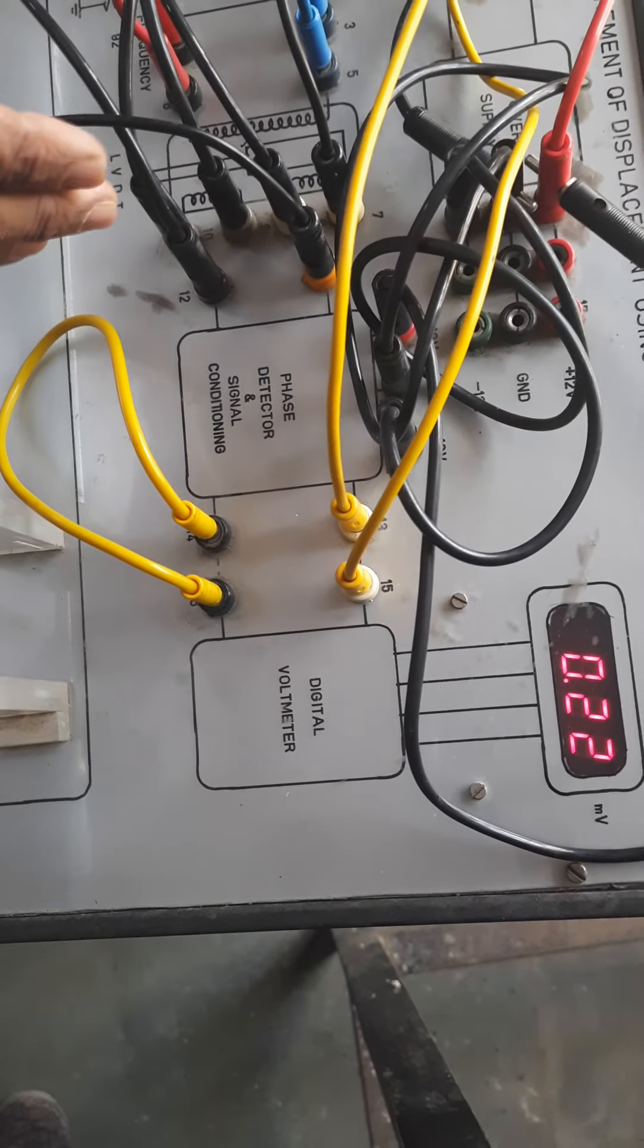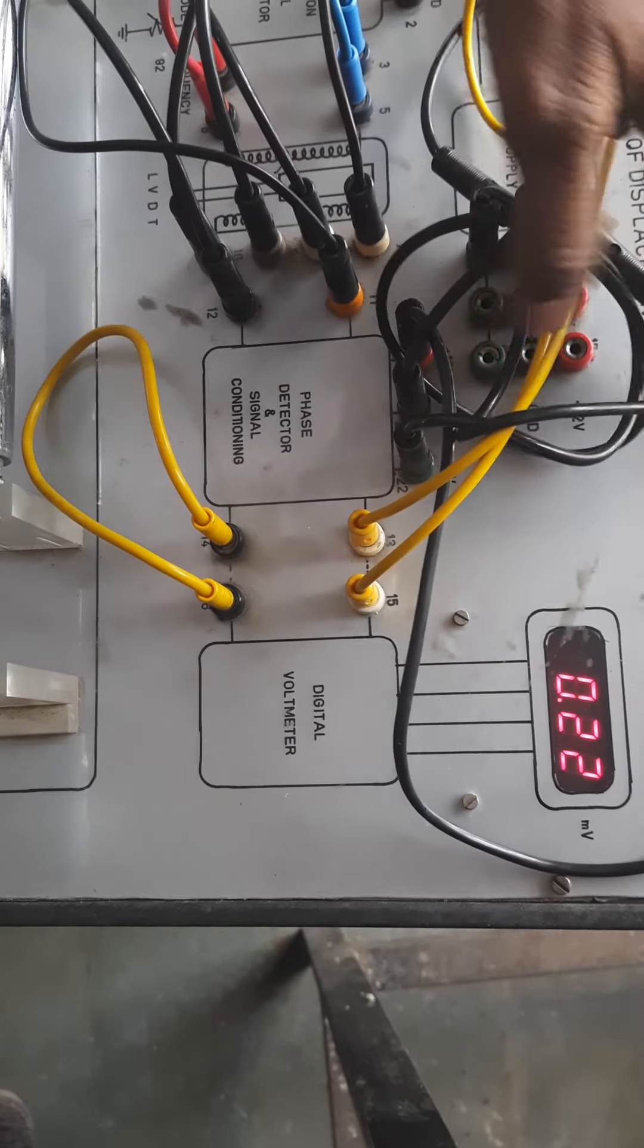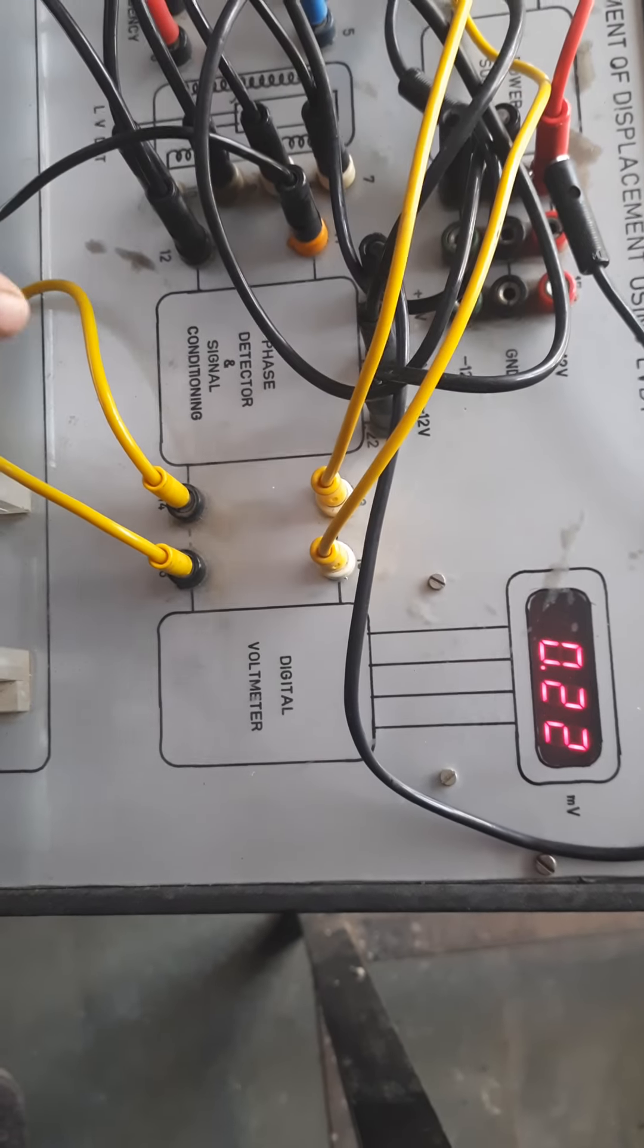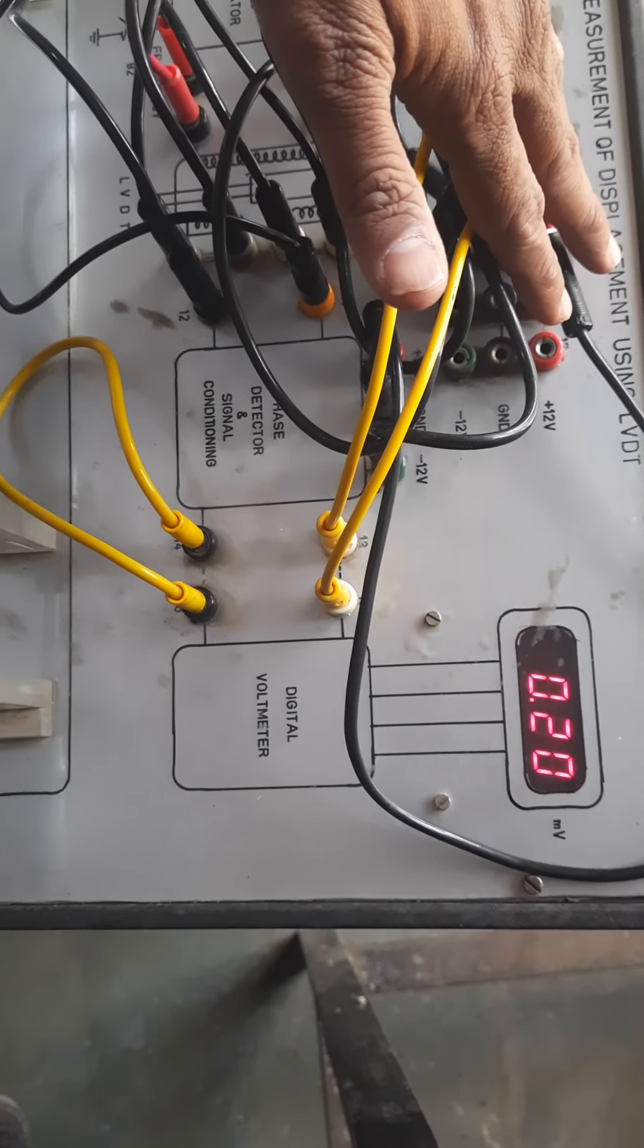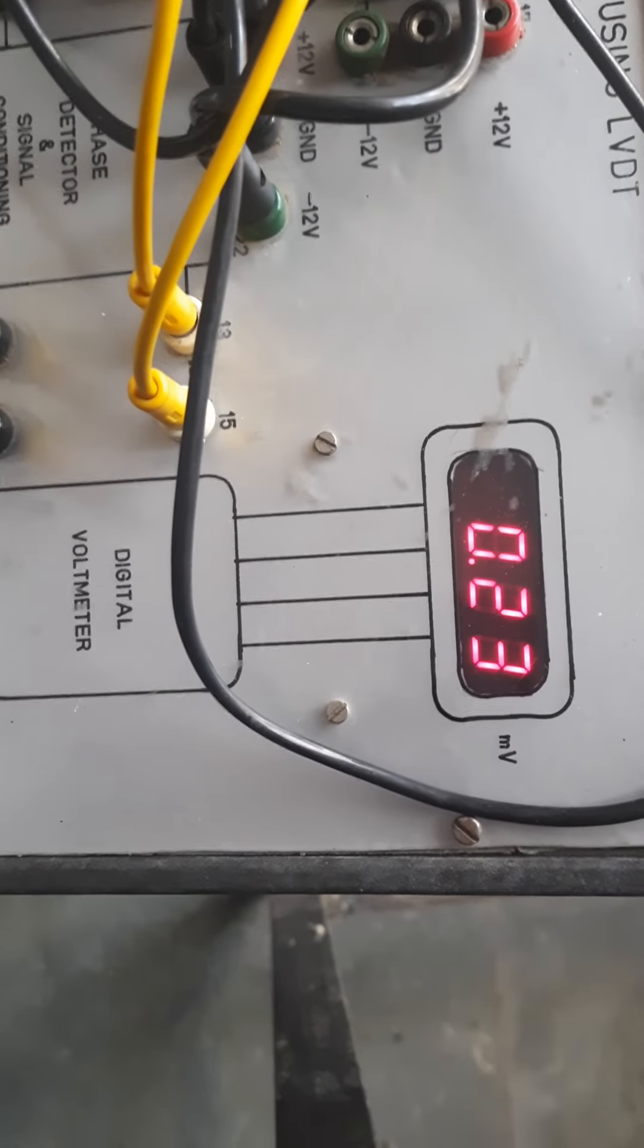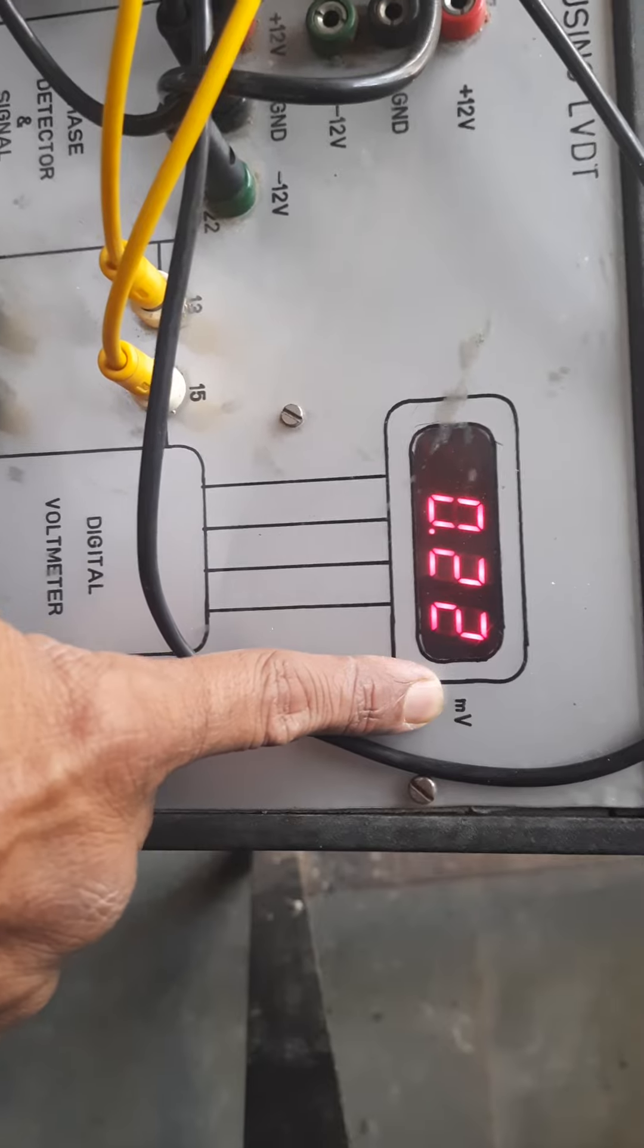Now, here we want to display in terms of digital volt. So as told there is a digital section, this is a signal conditioning block. It will condition the signal, right, and it will give to the digital voltmeter for the display purpose. So this is a DVM section and this is signal conditioning section. This section also requires power supply for its operation. So we are taking it from the power supply. So that is for this connection. And right now, you can see there is a reading of the voltmeter. It is near to zero. Now, in order to move the core, this is in millivolt, remember, 0.3 millivolt we'll make it zero also.